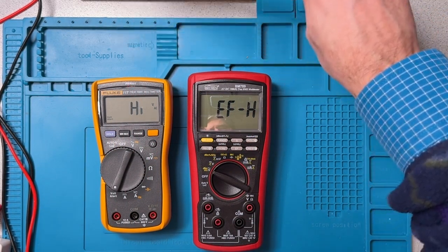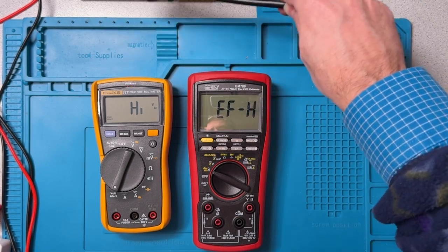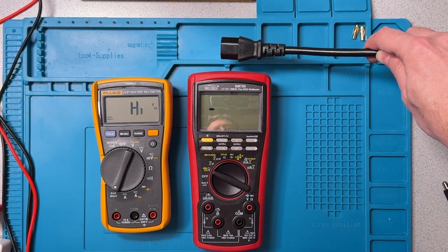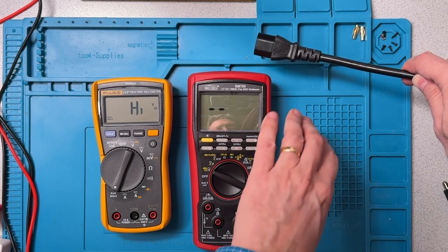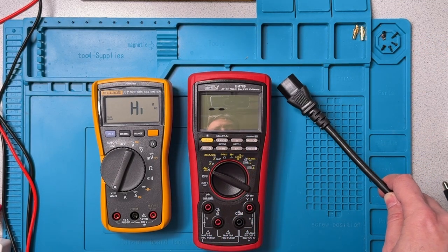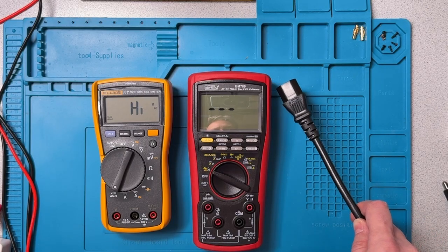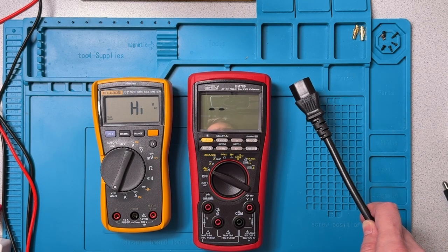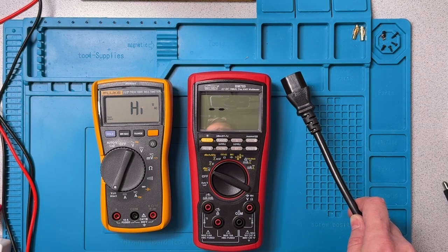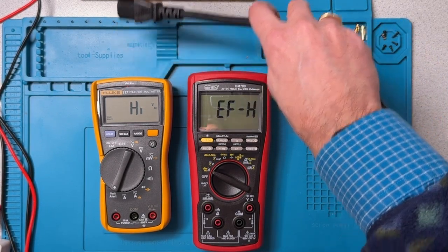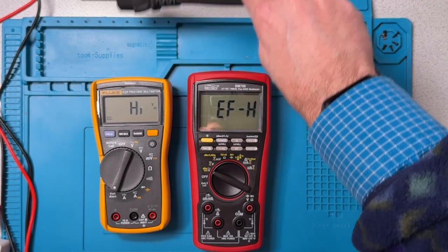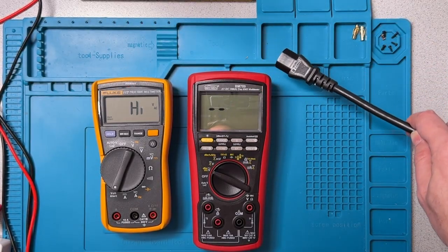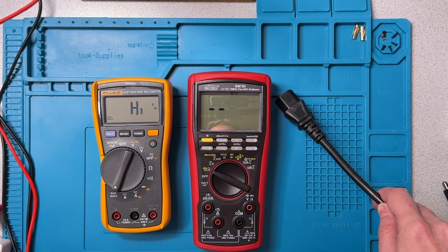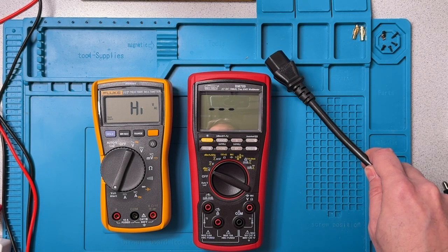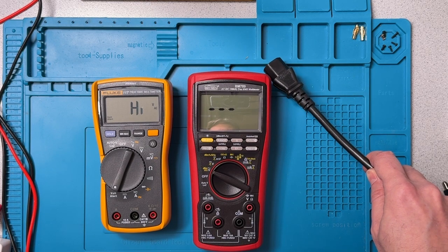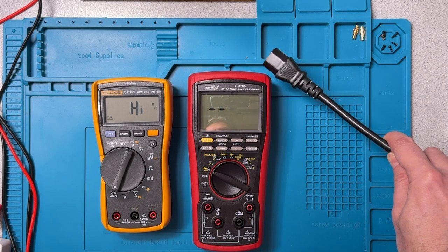And as I bring these across, you can see the Fluke is very sensitive. The Brymen starts to beep. The sensor for the Brymen is over here on the right-hand side. And as I bring that to the sensor on the right-hand side, you can see, similar to the Fluke, although the Fluke doesn't show any level of intensity. It's just there's voltage there or not. Whereas with the Brymen, we get a bar graph, if you will, and a beeping depending upon how close the hot is to the sensor.